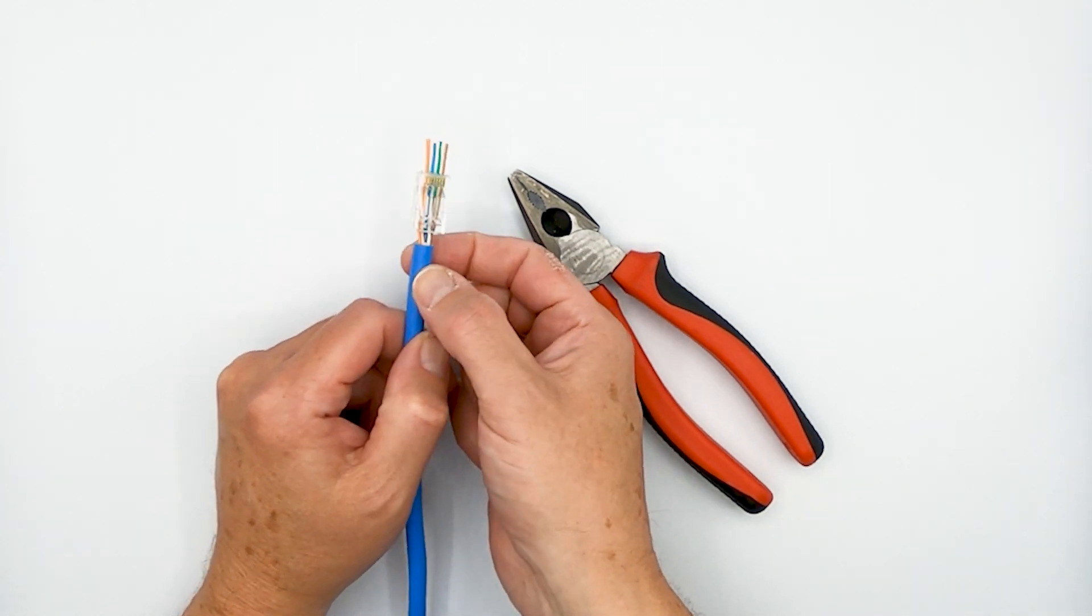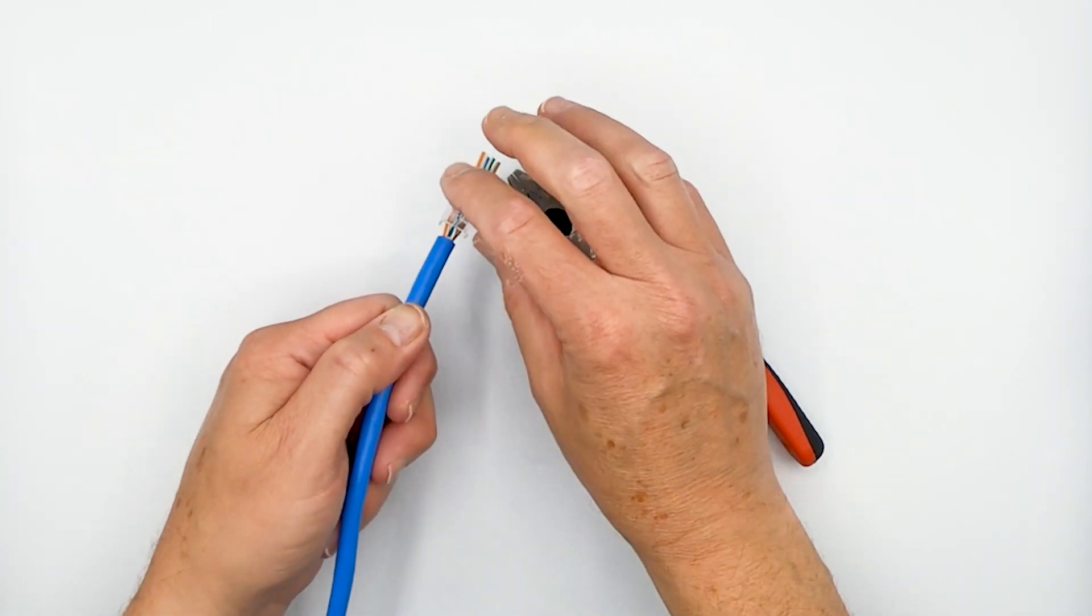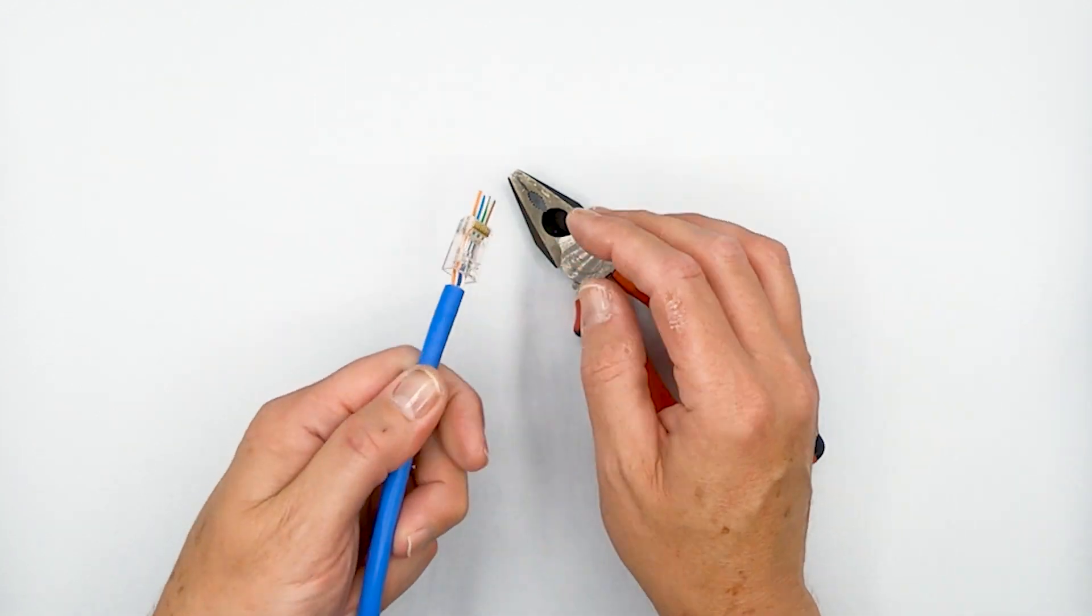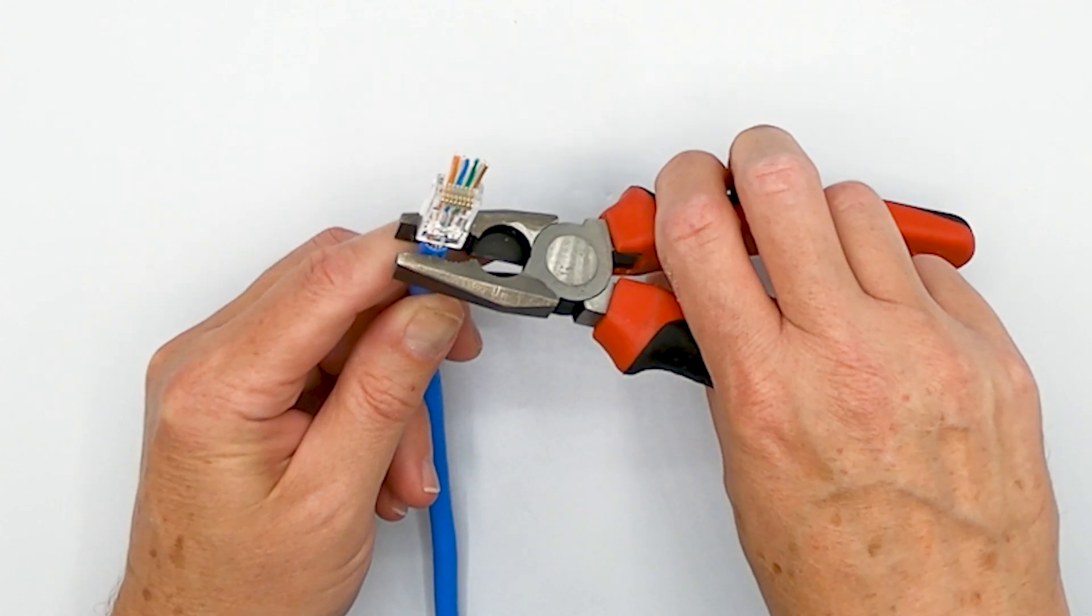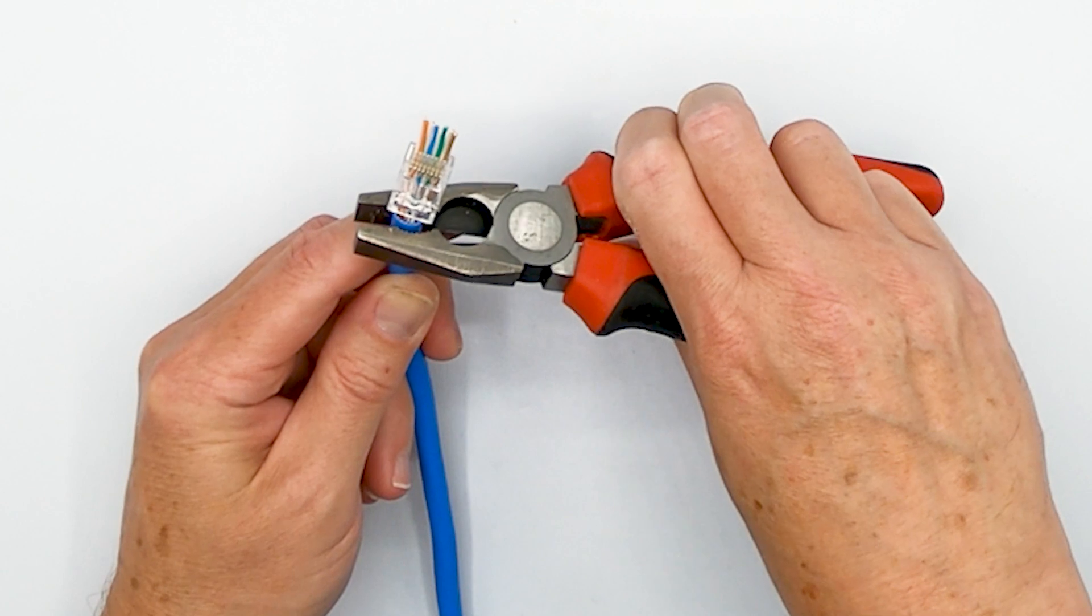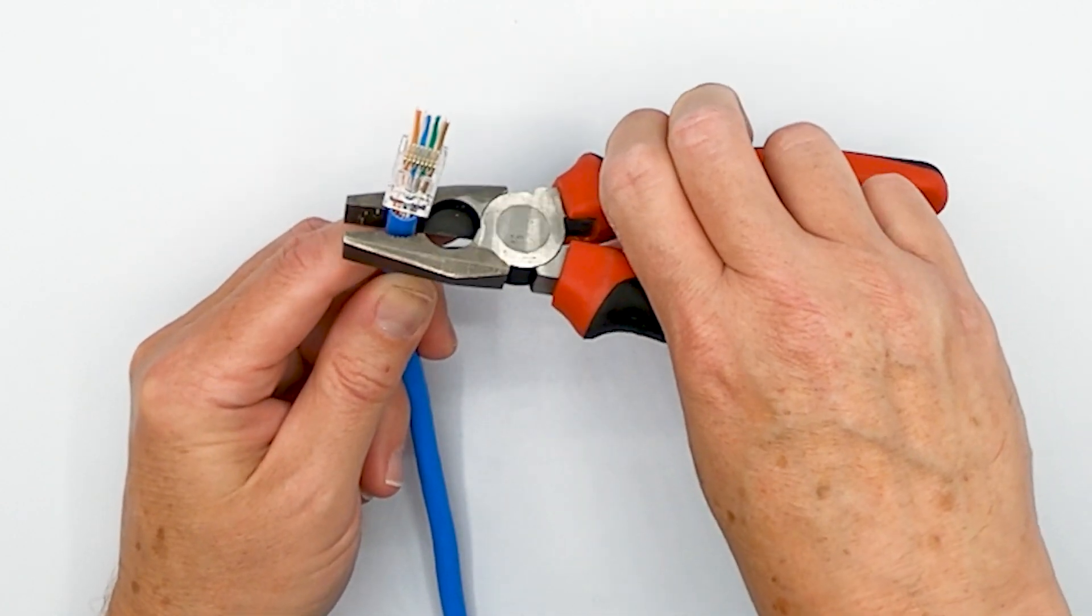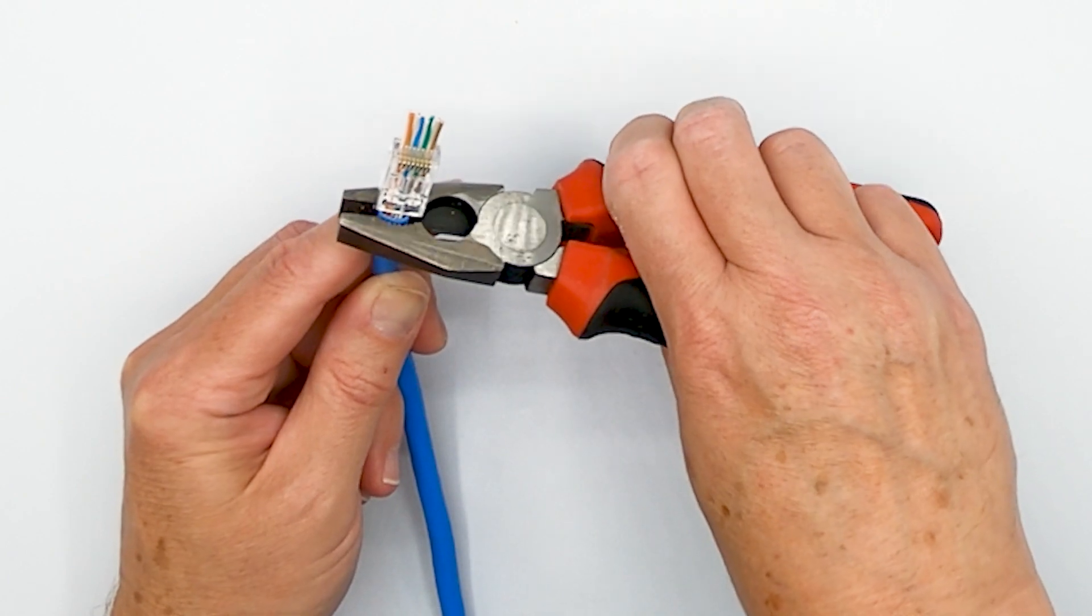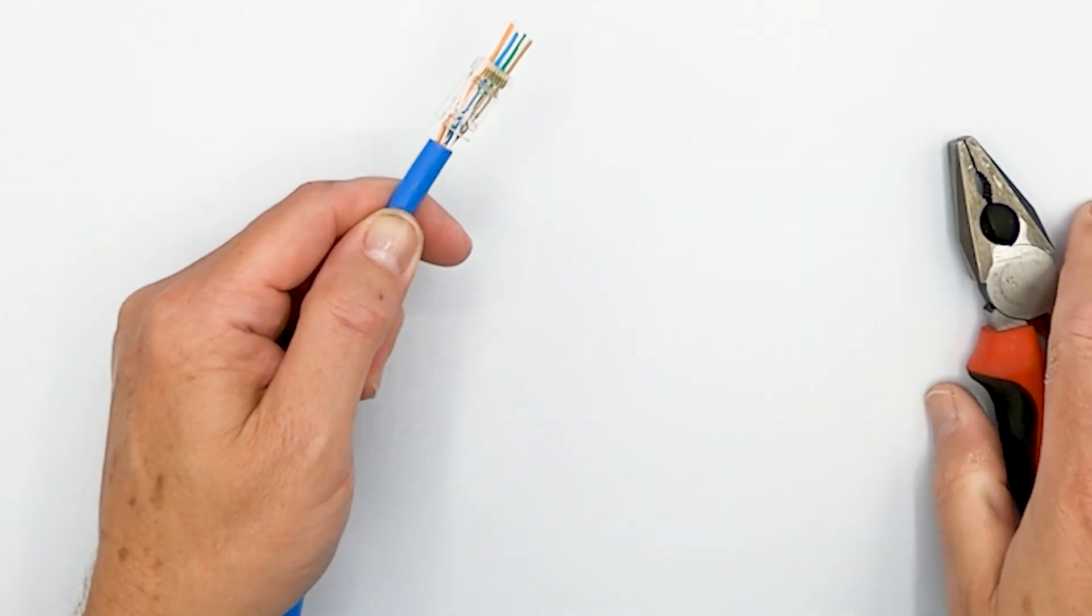The idea being to shape the end of the cable gently to match the rectangular cutout in the back of the plug. So, I'll demonstrate that right now. So, you're going to shape it in line with the plug like so. And the last half inch is more than sufficient to ovalize. And don't go smashing it flat. All you're doing is looking to gently reshape it. And that's all that you want to do so that you make this process easy.